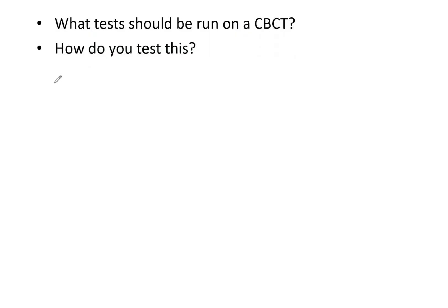Today, let's talk about cone beam CT and what tests you should run on the system and how to do those tests. This is something that not all physicists are familiar with. Different clinics do different cone beam CT tests, and unfortunately some probably don't do any QA on them, but it is necessary and mandatory that you test these. We have daily, monthly, and annual tests that need to be run on the cone beam CT for our linear accelerators. You should be able to verbally discuss these in an open forum easily and in detail, especially if asked on the oral exam, so know these well.